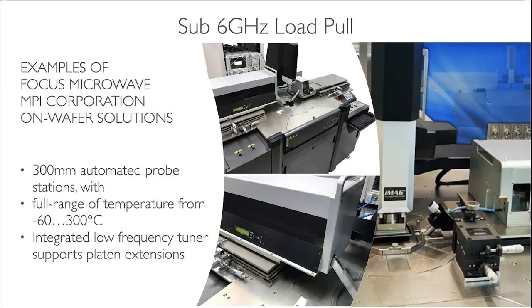To accommodate this, you need to move the tuner. You can't just use a small positioner to move the probe, because even if the tuner is fixed and you move the probe, even if it's micrometers, you're still moving a bit. You do a calibration, you need to do a TRL calibration, so you need to open it up for a delay line. So the device has a different pad distance, and you're still moving that probe tip a bit. The more you move it, the more it will introduce uncertainty and phase error. Here's an example in the middle and at the bottom, where the tuner is actually residing directly on the positioner, but we'll show that in more detail after.